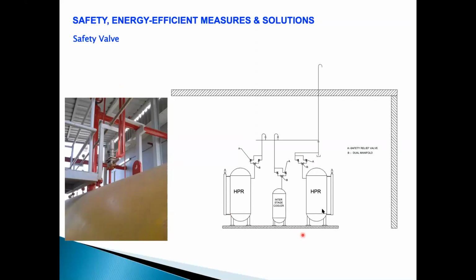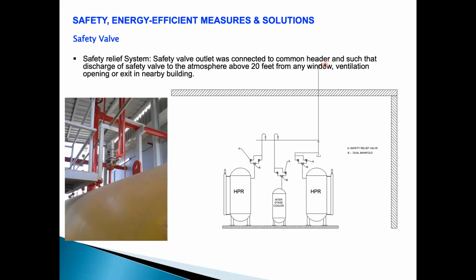What is the proper way of releasing the safety valve? Make one common header, connect all your safety valve outlets to it, and take this pipe outside. This has to be at least 20 meters higher than any nearby window or door where human beings are accessible, and you release into the air. Ammonia gas is lighter than air. When it mixes with the air, ammonia does not have any life in the atmosphere, so it immediately dissolves into air. And once ammonia is mixed with the air, the toxicity of ammonia becomes non-effective. So if you design a proper release system, there are no effects of ammonia.